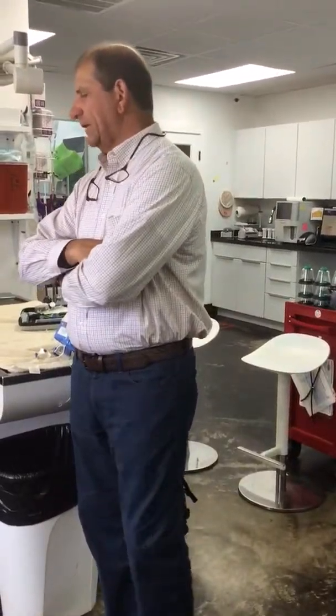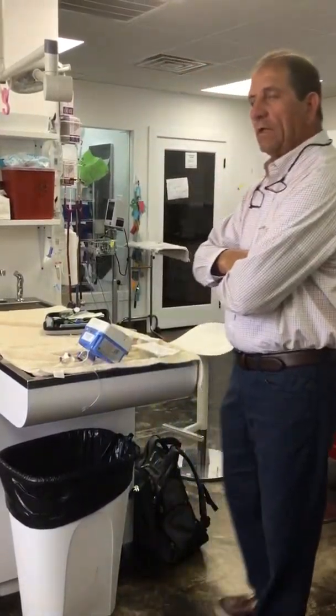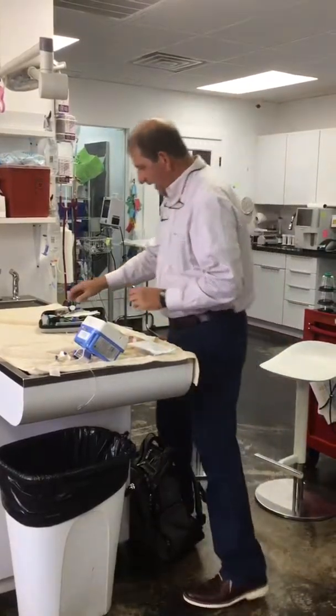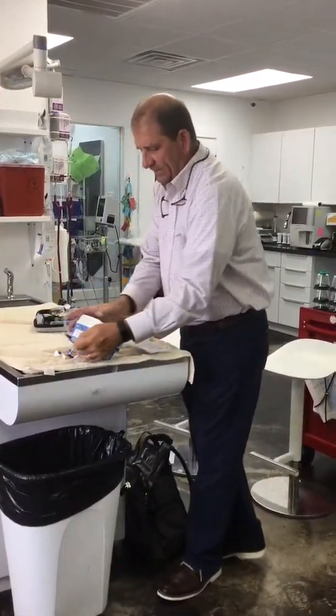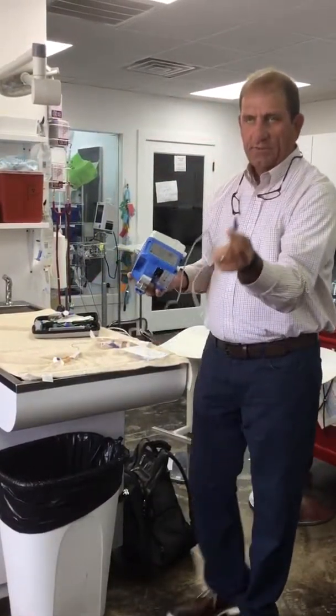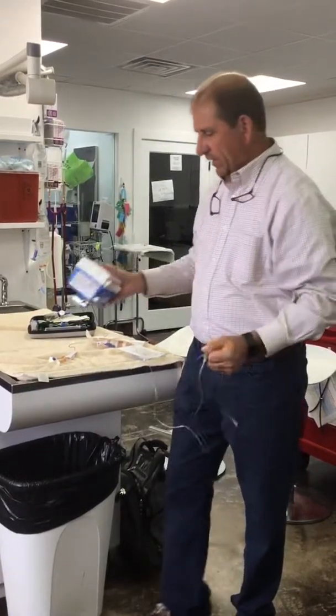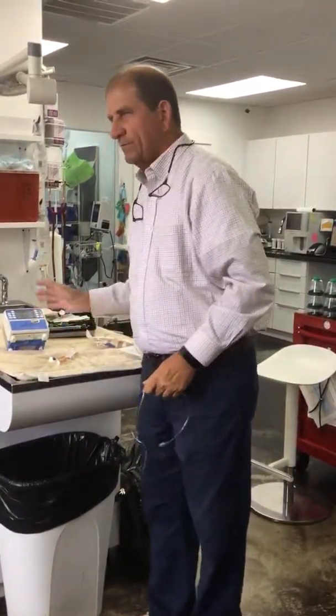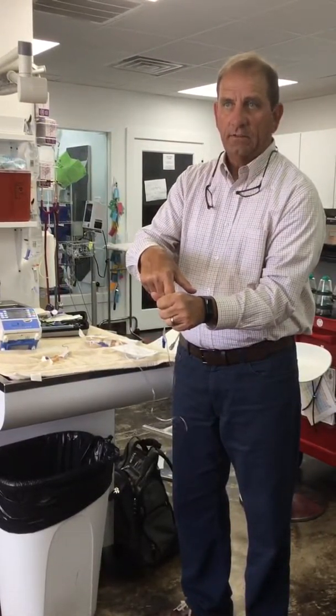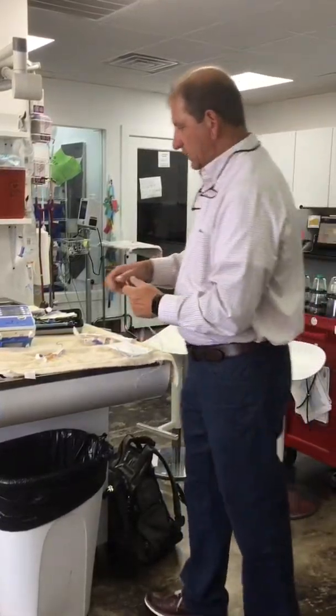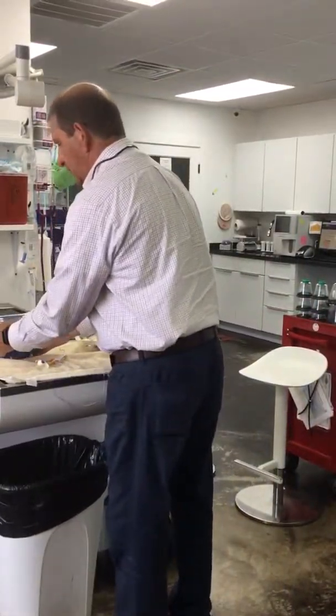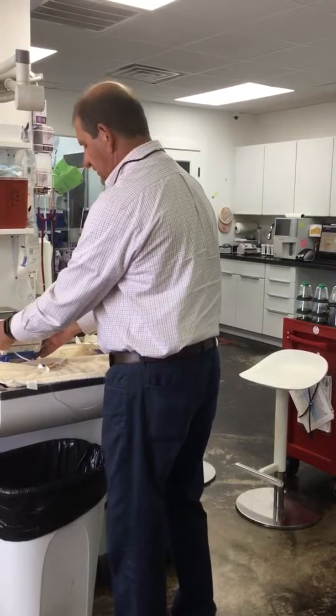The whole pump. Can you run it with a syringe attached and just a line on an extension set? You can, but you have to run it with this tubing, and you're gonna have some. See the needle free? Okay, so if I wanna do a syringe infusion, the problem with the needle ports is you don't have the connection, because you got just that needle stuck in there, so it's not really tight. Correct. So if I wanted to do a syringe infusion, we have a lot of customers that do this.